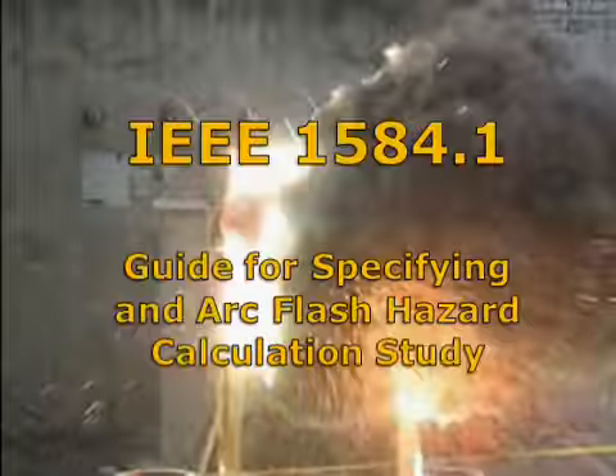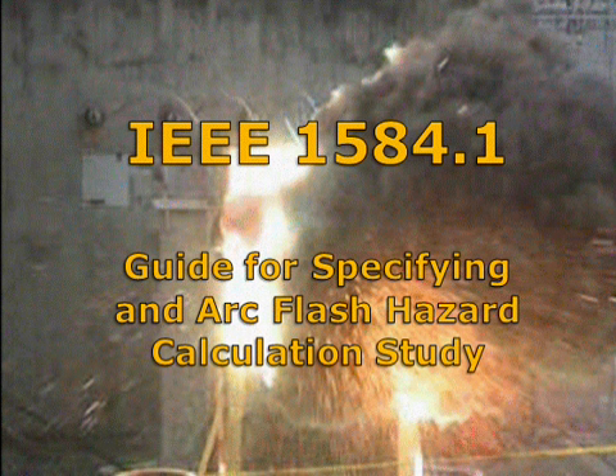And then there are a series of equations for the arc flash in air, spherical equations, and arc flash in a box. And so there was a paper presented about a year and a half ago that was an extremely good paper that gave us some forward movement on DC arc flash calculations. I mentioned IEEE 1584.1. This is a guide for specifying arc flash hazard calculation studies.